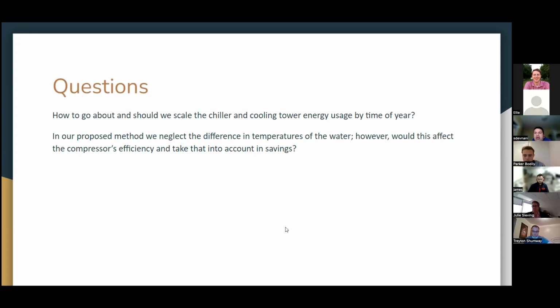On the cooling tower, it would just be, my cooling tower is rated for 100 tons and I have 70 tons of heat to reject. So it's cycling at 70%. You could just use a 70% multiplier times your fan horsepower, or you could subject it to a fan curve with a VFD, and you can calculate the energy use, just assuming that if 70% of the load is there, it's going to cycle on only 70% of the time. That's a reasonable assumption to make in energy analysis.